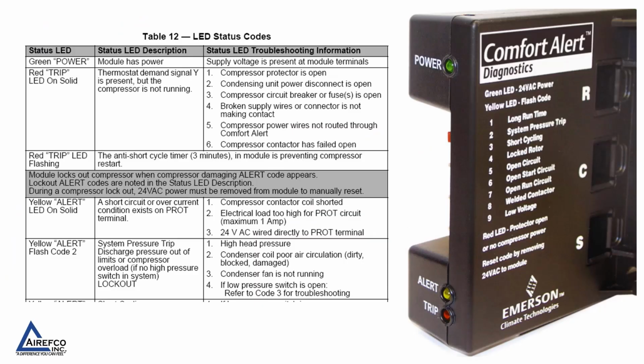This table, which lists the LED status codes, is available in the user manual, which is easily downloadable from the internet. It shows us the green power LED, which tells us the module has power and supply voltage is present at the module terminals. The red trip LED, if it's on solid, tells us that we have a demand on Y for the compressor to run, but the compressor is not running. If it's flashing, this tells us that the anti-short cycle timer is preventing the compressor from restarting. The yellow LED, if it's on solid, tells us that we have a short circuit or an overcurrent condition on the protection line. If it is flashing, it tells us that one of our safety switches has tripped and the unit is put in a lockout condition.